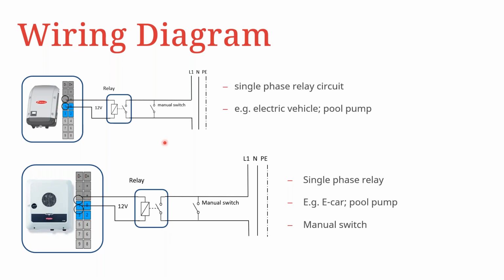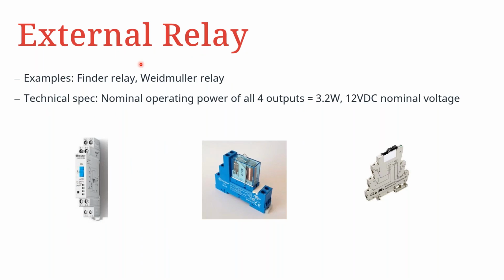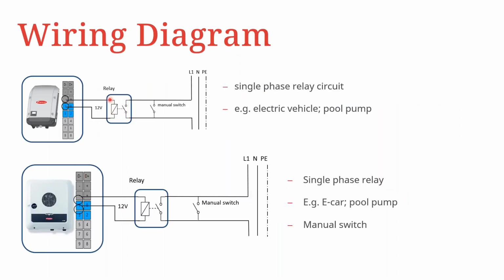When it comes to the external relay that is required, we have some examples here. This is not exclusive, these are just examples. We have the Finder relay, for instance, and the Weidmüller relay, and the technical specs. What you're getting from the Pilot or the Data Manager is a 12-volt signal and a maximum of 3.2 watts. So what you should connect in this particular area is only a 12-volt relay. The relay should not be either 24 or 240 volts AC. That is not going to work with the digital IOs.